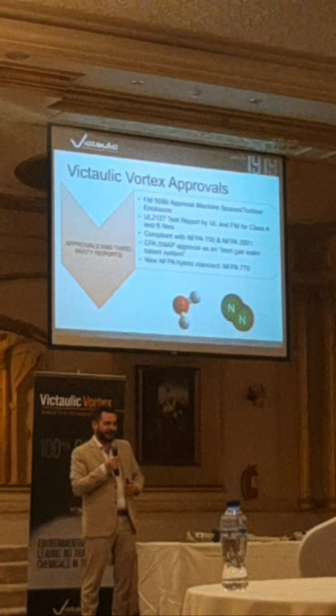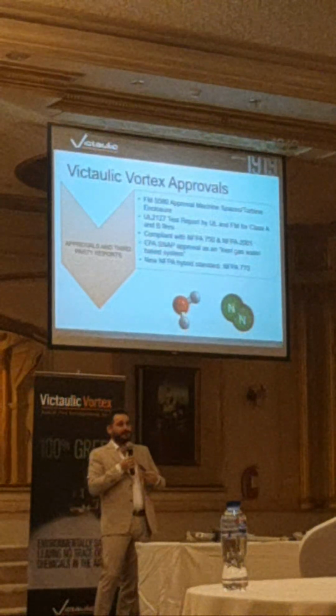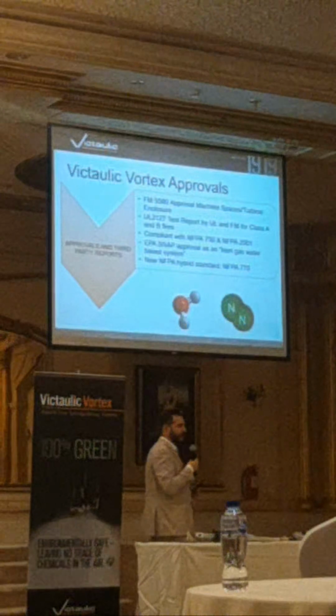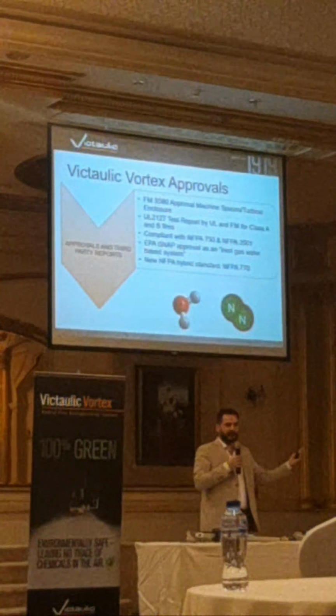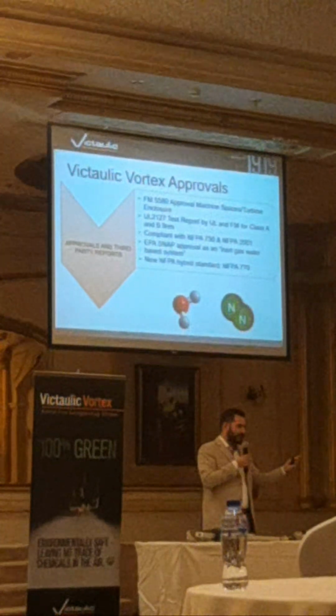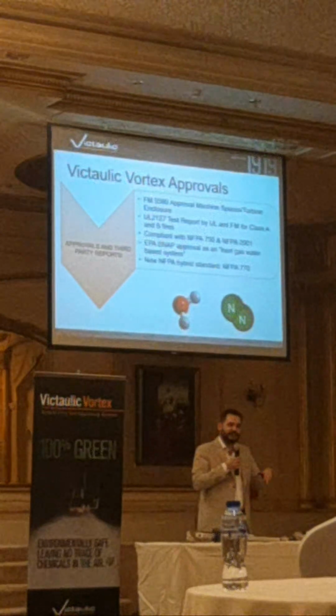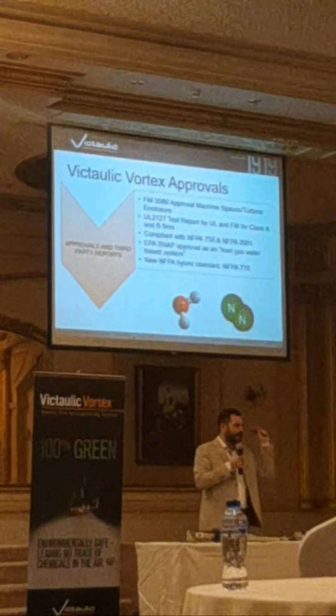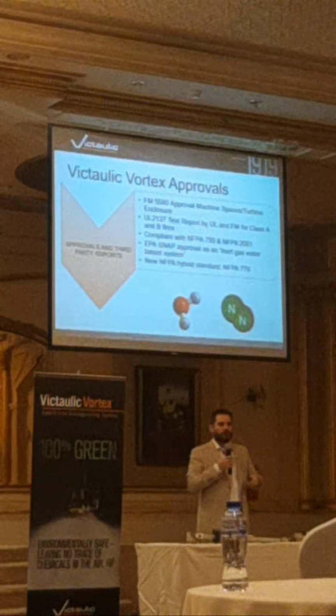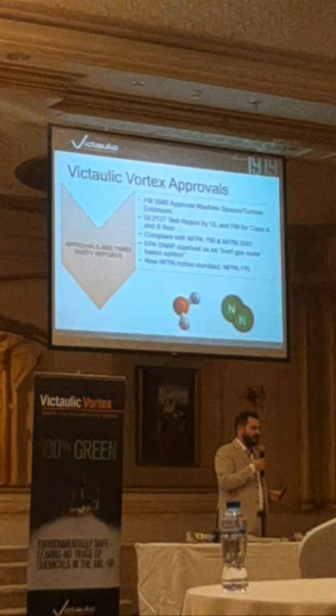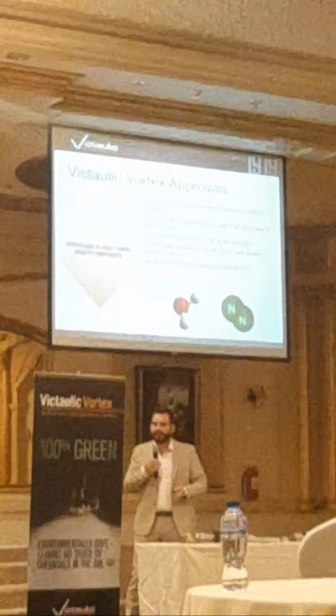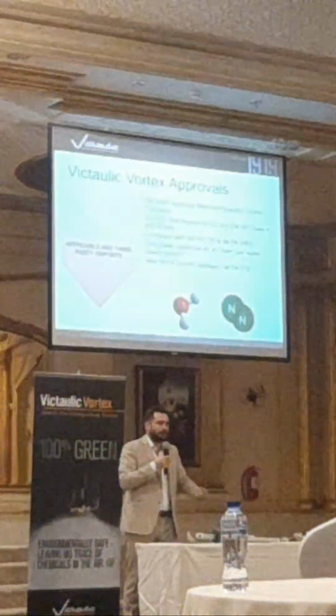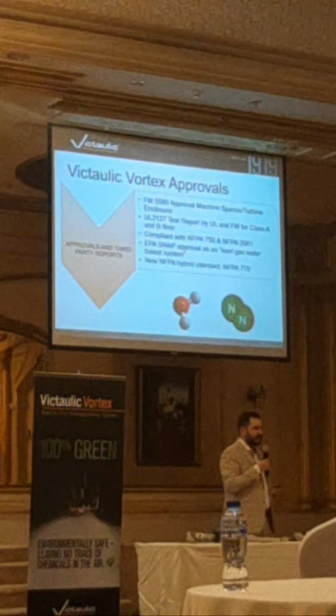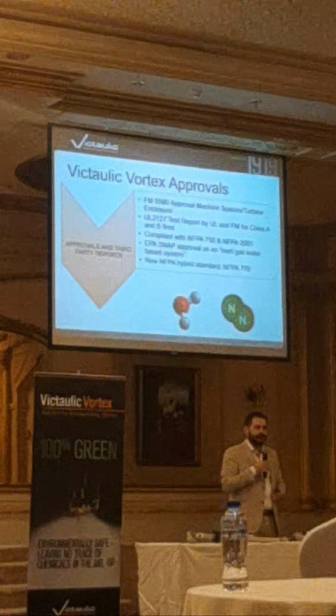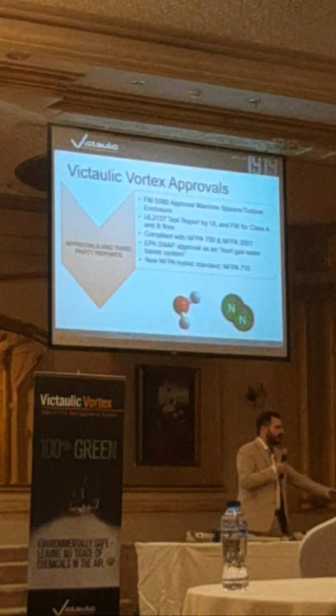However, because we were considered, in their eyes, a water mist standard, they didn't really think about the gas that was added. What do I mean with that? They basically took their standard for water mist, which was FM 5560. They did a Control F search for every time water mist was mentioned, and then did a Control replace all, changing it into hybrid water mist. So the standard that we had was basically the water mist standard. The issue there is it didn't mention gas, it didn't mention room integrity. For us that was a bit of a downfall, because the biggest advantage that we had, we couldn't really prove to anybody. Then we did testing with UL, for the clean agent standard. We were also successful, but the same issue: there's no mention of water in that standard, so it cannot be used according to the standard.